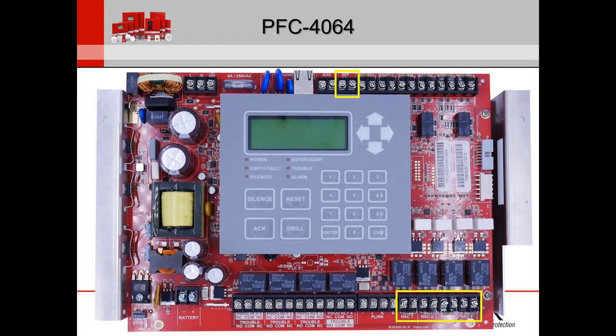A question about a specific enunciator: the 4064 does not use a specific enunciator. You can use the RA 6075, or you can use the 6500. My preference would be the 6500 because many codes, especially at the jurisdiction level, say the remote enunciator must mimic or exceed the display of the fire alarm control panel. The 6075 is a 2x16 character display, while this panel is 4x20, so it probably wouldn't comply. The 6500 is actually about $8 cheaper than the 6075 despite being the larger display.